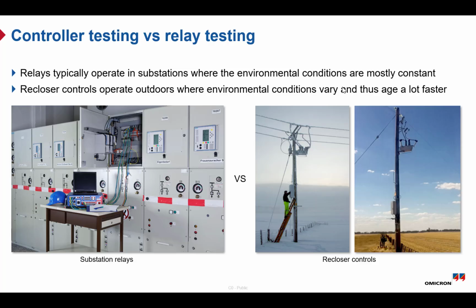But with recloser controllers, it's different. They are installed outdoors where the environmental conditions can vary, like heat, dust, or humidity, and this can affect the equipment over time. Also, testing in the field is more time sensitive. You often need to complete the setup and testing quickly. That's why fast and simple connections are very important.